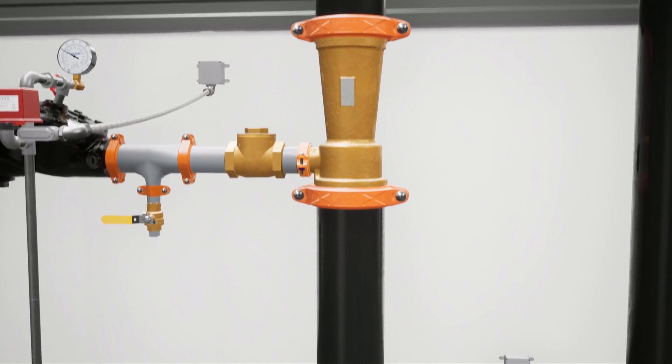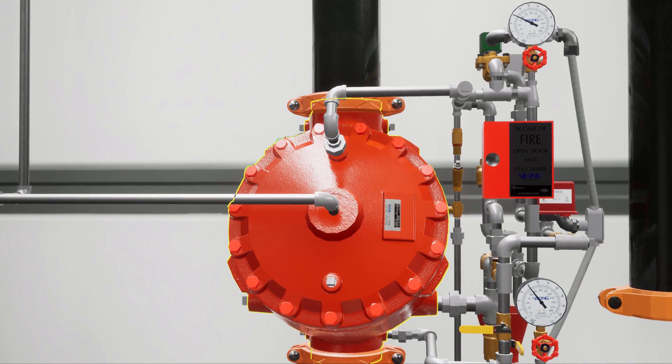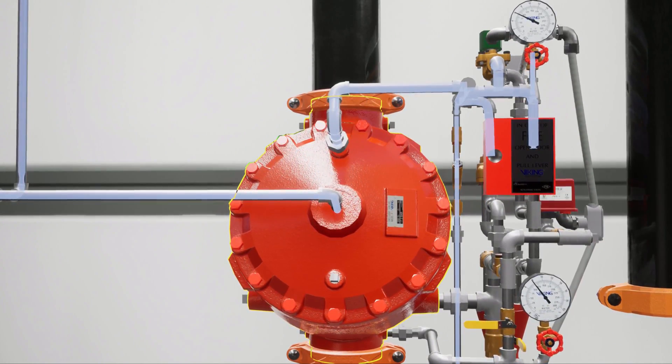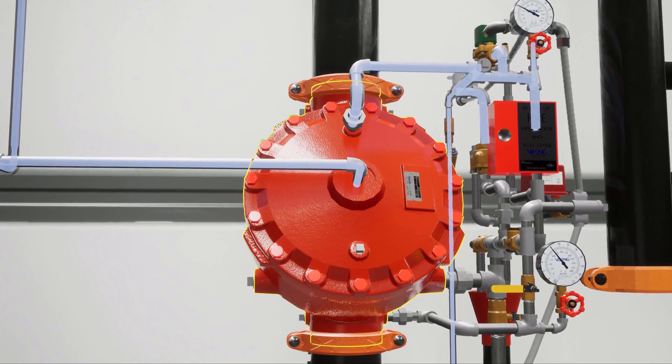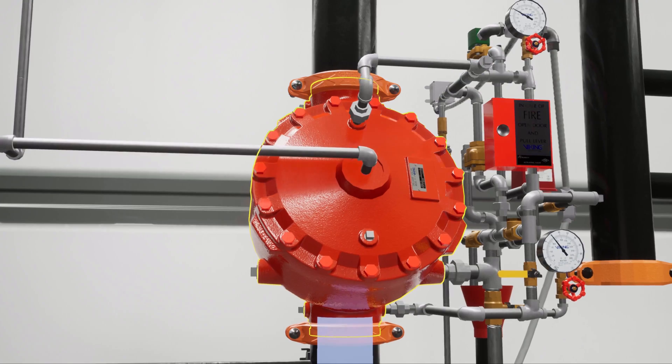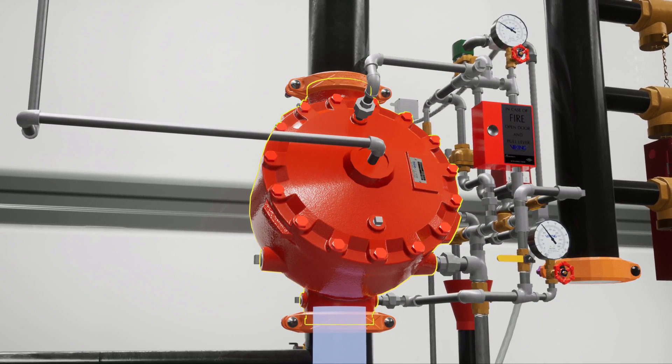Upstream from the ratio control valve is the F1 deluge valve, which has a shared priming connection with the concentrate control valve. This allows the two valves to activate simultaneously. The deluge valve is holding back the main water supply until the system is activated.